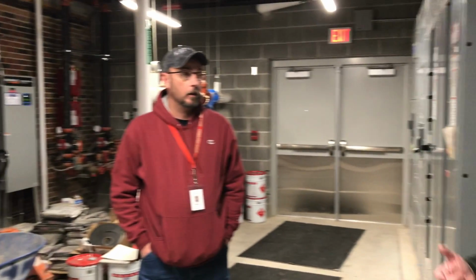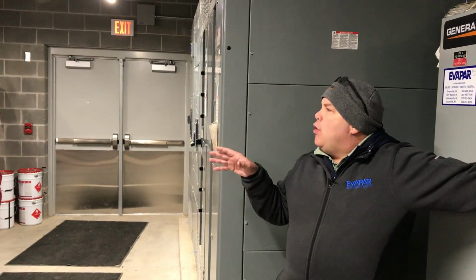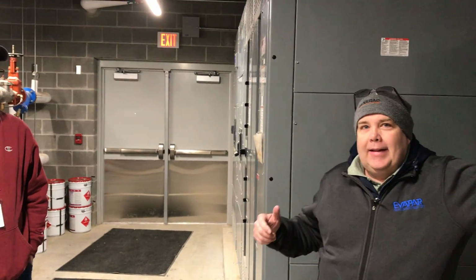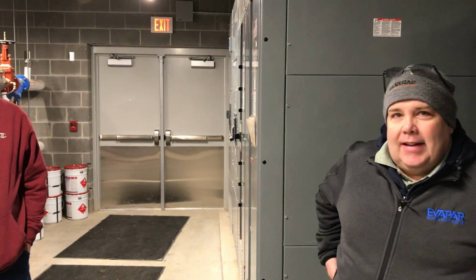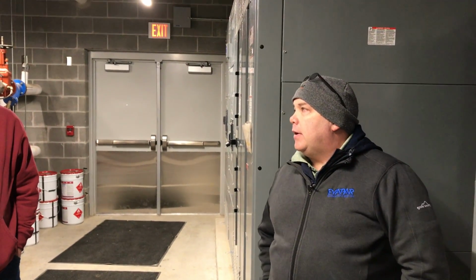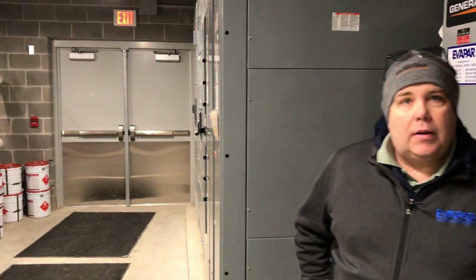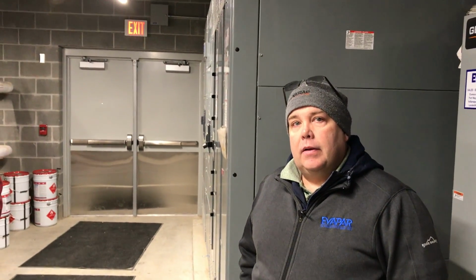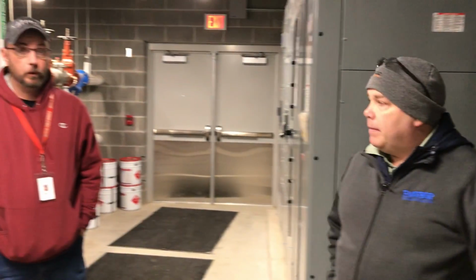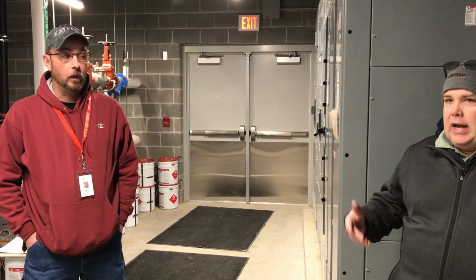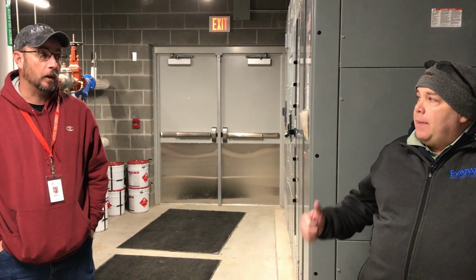How long does it take for an alarm to go off? We can talk about it later, I'm not terribly worried about it. It still might just set the alarm off, something we need to remember, that if we have a power failure here, we're gonna have to reset the alarm in the generator. How many seconds is it before the power comes on when it transfers? About 7 or 8, less than 10. Is that enough time to still set the alarm off out there? Down around 6, it's quick.